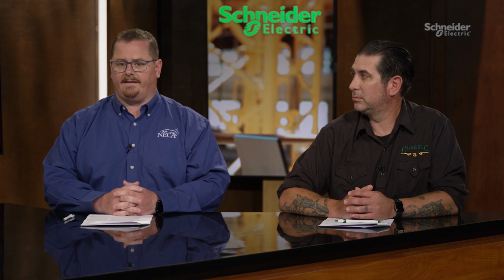It also ties into our discussions about maintenance and qualified workers. When you're maintaining electrical systems and performing routine service and maintenance, and you have to replace an overcurrent device, if you don't do that with a like device, now you've just altered that selective coordination study, and that system might not be as reliable as it's required to be. So that's where the qualified worker part comes in, making sure they understand the impact they're having on that service and maintenance and that equipment.